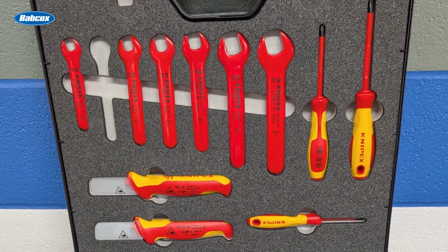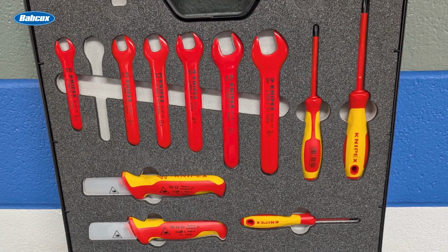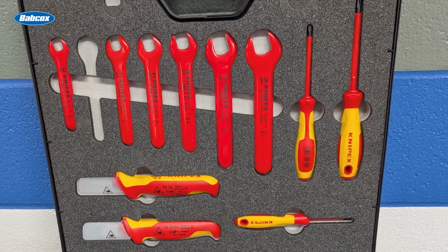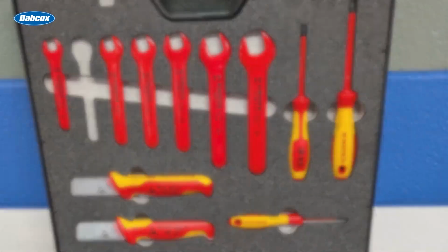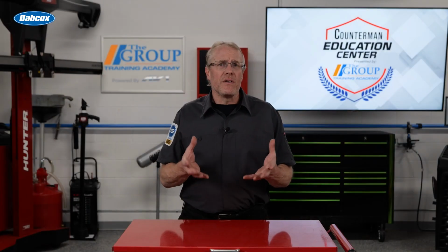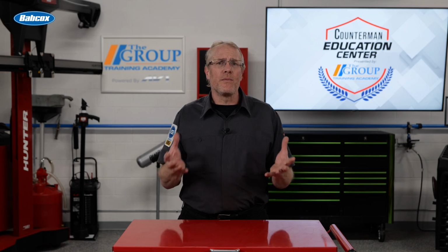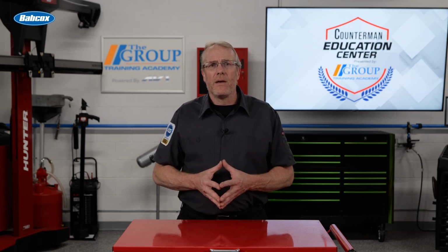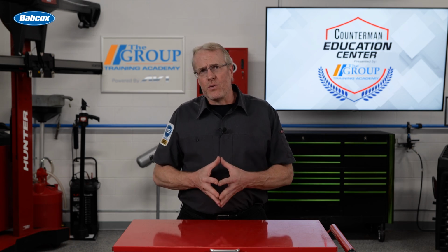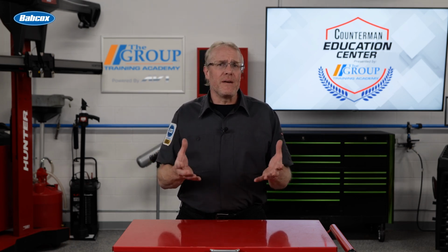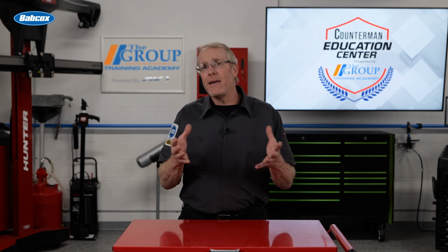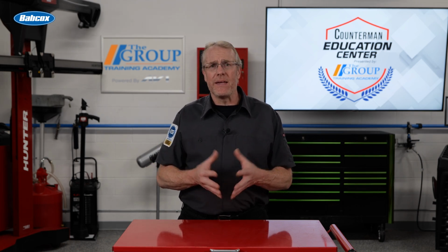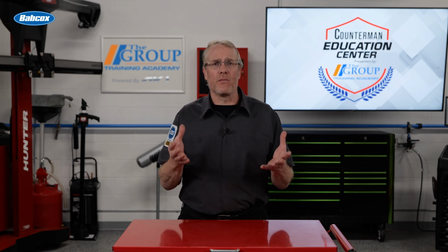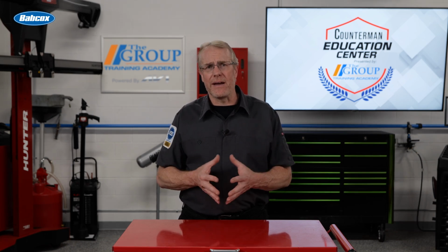An insulated tool is a regular tool, just like what we use now, but coated with a non-conductive material. Even if the tool itself conducts electricity, the insulation prevents it from flowing. The drawback to insulated tools is if the insulation is damaged or worn in any way, it can allow electricity to flow, and the insulation must be inspected on a regular basis to make sure it is intact.